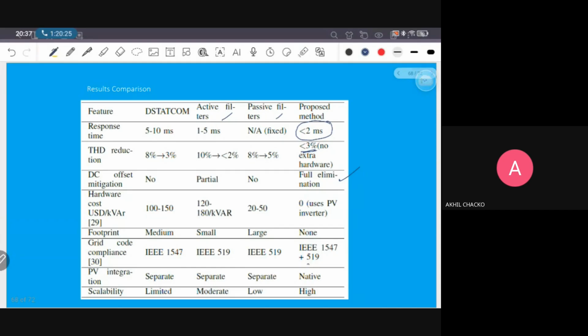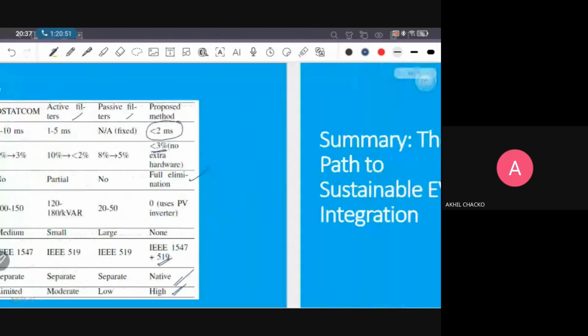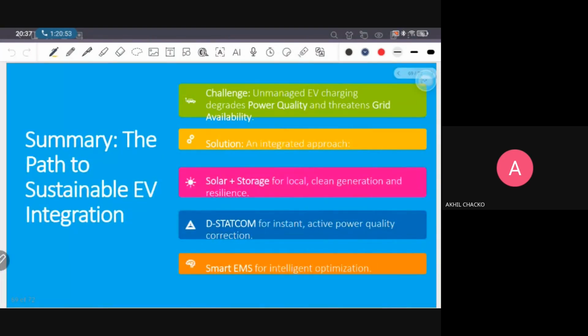And we have obeyed the IEEE 519 standard. That means the grid current THD is maintained within the 5% limit. PV integration is native with this technology, and scalability is high. We can scale this system to any power level by replacing the inverter and components. So, the path to sustainable EV integration.